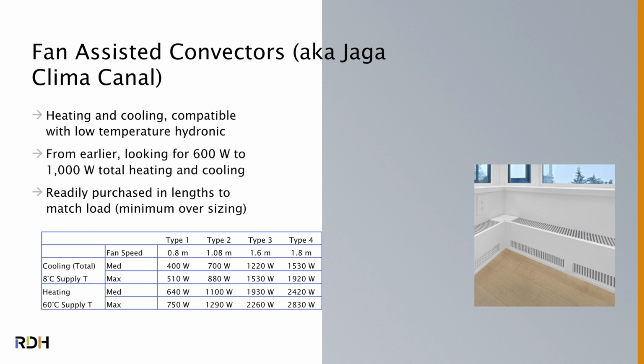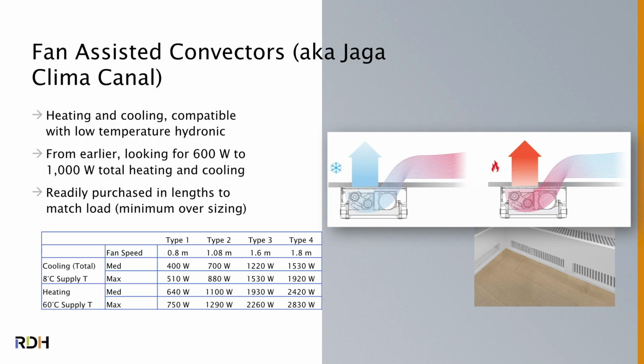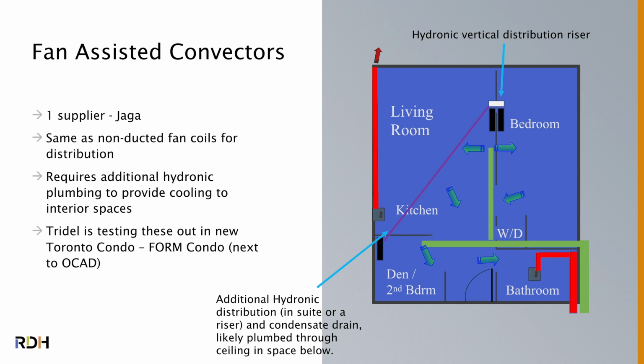They're called Jaga. Then there's some of the sizing that you would need and how long you would need it, to deliver this much heating and cooling. They're available in a trench. They're available in a more conventional looking radiator, but they're a pretty interesting option. This is how the trench would work, and like I said, they have a little fan in there. And how you would also distribute it, but again, you have that same problem. If you want to cool that inside space, you've got to find a way to put plumbing in there from your main riser, or put another riser in the building.